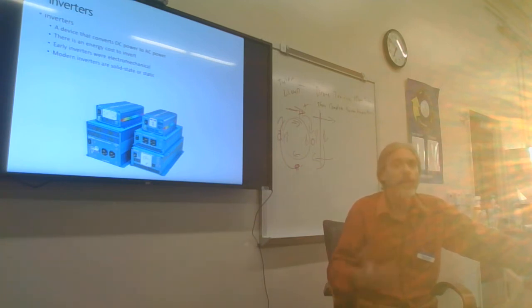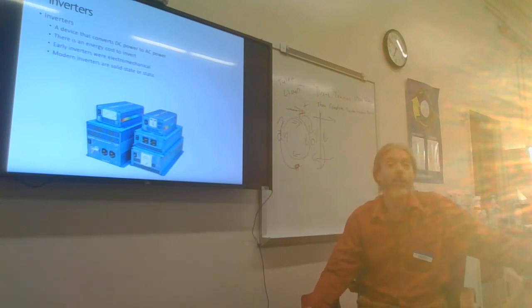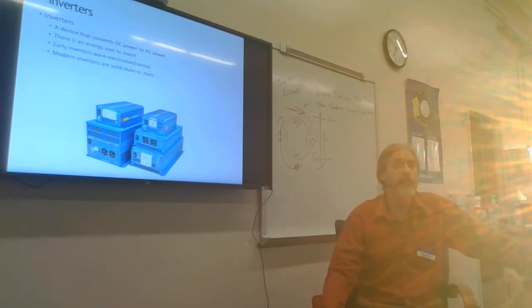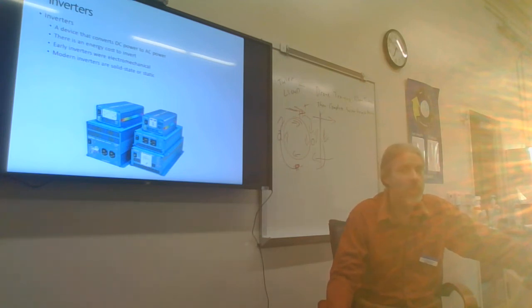Our inverters have gotten better and better and better. Whenever I started inverters in 2009, inverters had a 5-year warranty, and you could buy an extended 10-year warranty that would add about 25% to your cost. Today, inverters almost all have a 10-year warranty, and you can buy extended warranties up to 20 years. The average inverter that fails today is 14 years old. I know that that's a weird thing to tell you. That's not saying that the average inverter made today will only last 14 years. It's saying that the inverters that were made 14 years ago only last an average of 14 years.